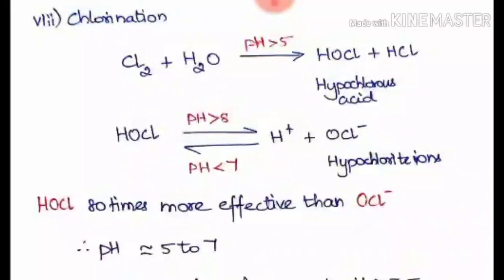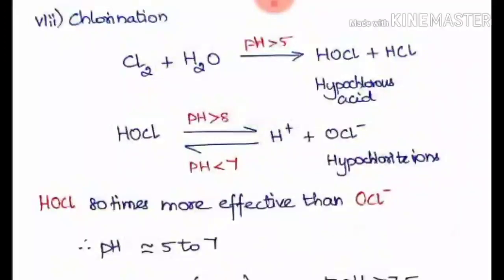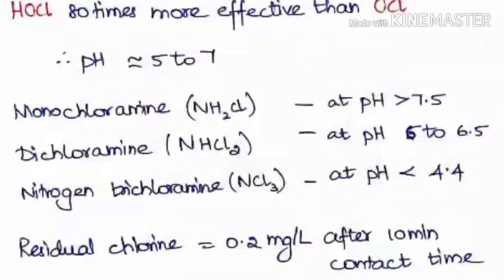If we sustain hypochlorous acid in the water the disinfection process will be more effective. By maintaining the pH in the range of 5 to 7, the dissociation of HOCl can be controlled to a greater extent so that the disinfection process can be done completely. Chlorine also reacts with ammonia present in the water and gives various products.